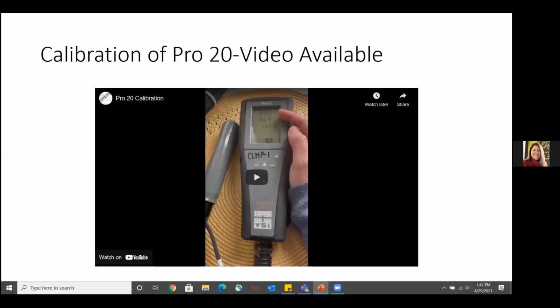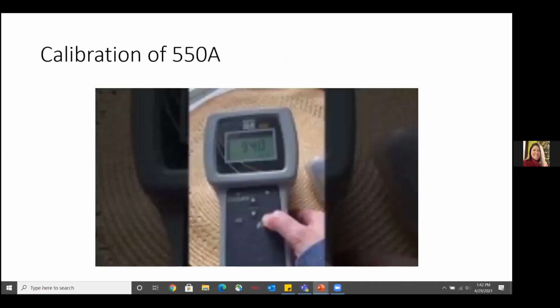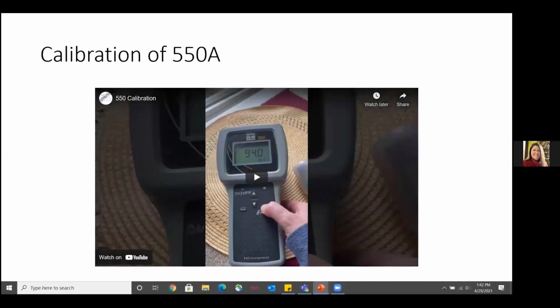I did want to note, before I go to the next one, what calibration is, because I didn't really talk about that. What we're doing is telling the meter, okay, when it's in air, it has a lot of oxygen, so the percent saturation of oxygen is really high. That gives it a starting point. When you turn it off and jostle the meter, it can throw that calibration off. That's why it's important every time you go out to calibrate your meter. So next we'll watch calibration of a 550A.